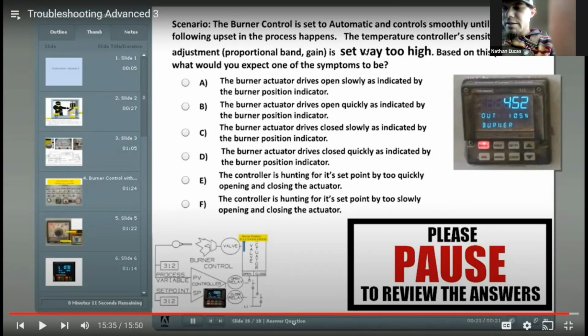My screen's blurry. So our controller sensitivity adjustment is set way too high. Do you think that's going to cause it to open or close quickly or slowly? Or do you think it's going to make it hunt, keep opening and closing? I actually think it would close pretty quick. I agree with you, but I think it's going to do it so quickly that it's going to go farther than it wanted to. And now you went beyond your set point. Right. And so now it's going to do the opposite. Now it's going to start opening really quickly because the sensitivity is really high. Now you went past your high set point. Now you're going to go back closing again. So do you think it's going to be hunting really quickly? Yes. I do too. Now, remember what I told you to fight this in case somebody comes in and adjusts them?